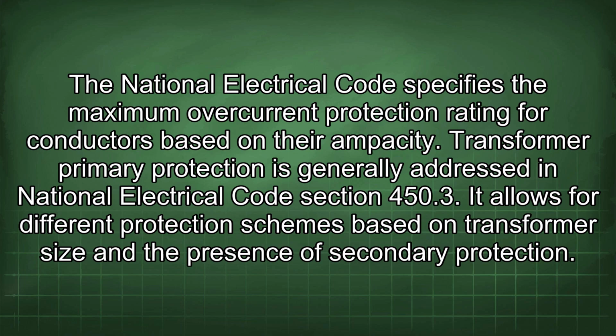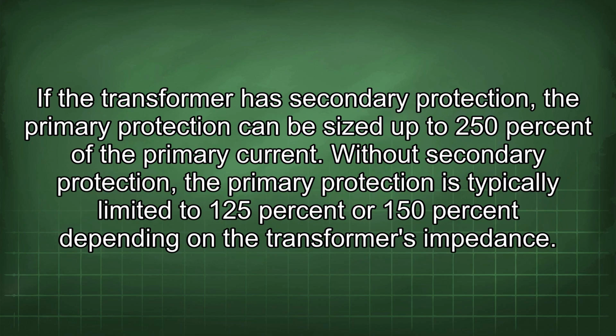Transformer primary protection is generally addressed in National Electrical Code section 450.3. It allows for different protection schemes based on transformer size and the presence of secondary protection. If the transformer has secondary protection, the primary protection can be sized up to 250% of the primary current. Without secondary protection, the primary protection is typically limited to 125% or 150% depending on the transformer's impedance.